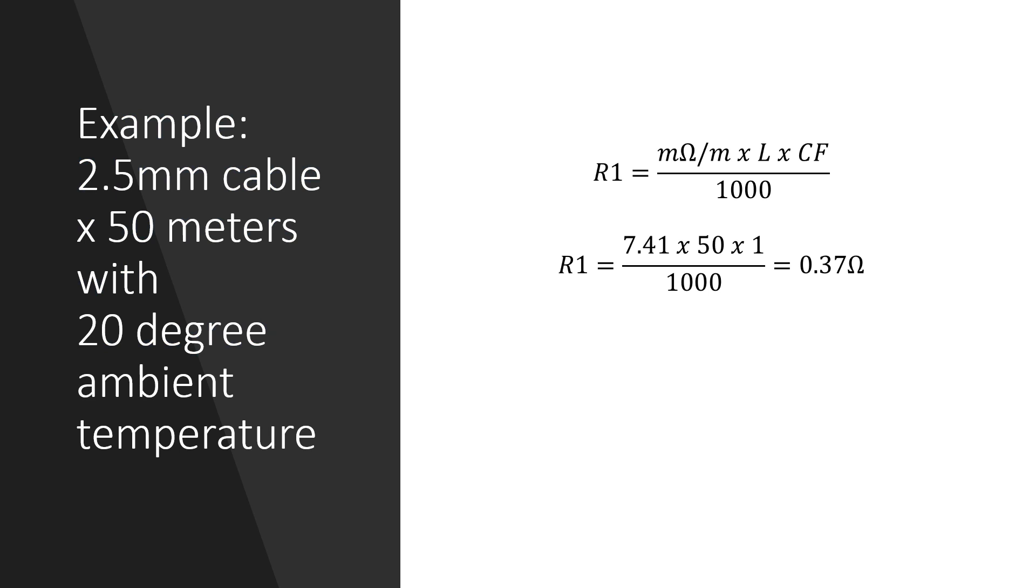So for example if we know that we have used 50 meters of 2.5 millimeter cable we can take the value of 7.41 milliohms per meter multiplied by 50 and then divide by 1000 which will give us 0.37 ohms. As I mentioned previously the correction factor for 20 degrees is 1 because the values are based on 20 degrees.